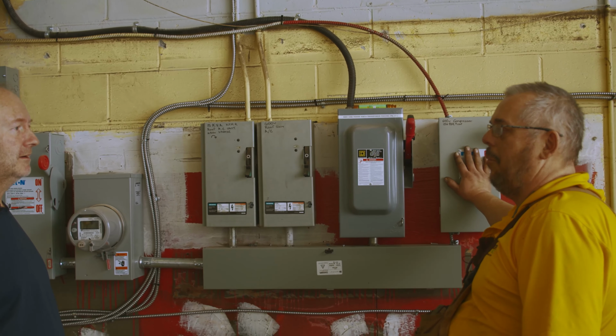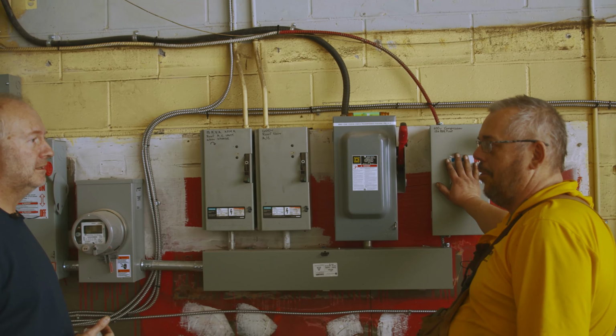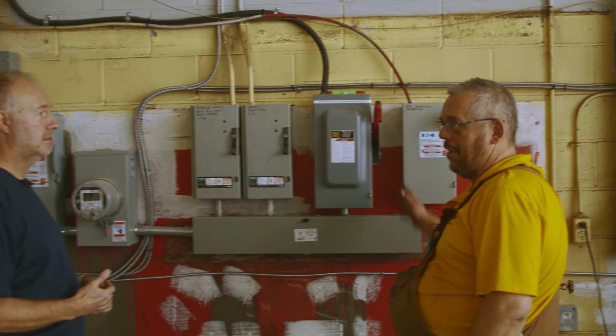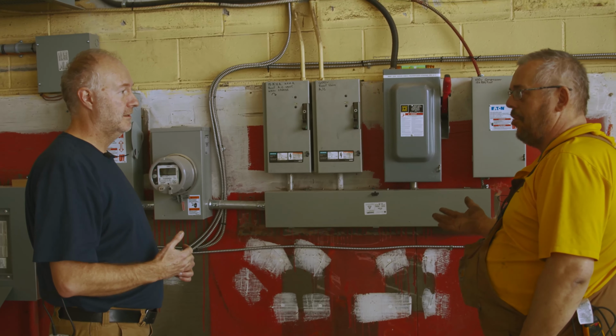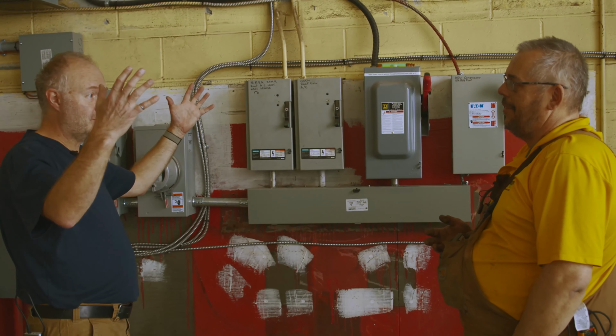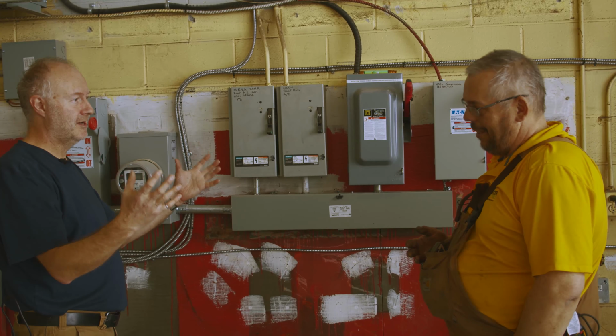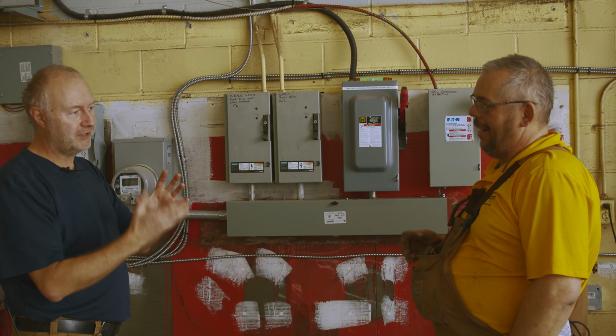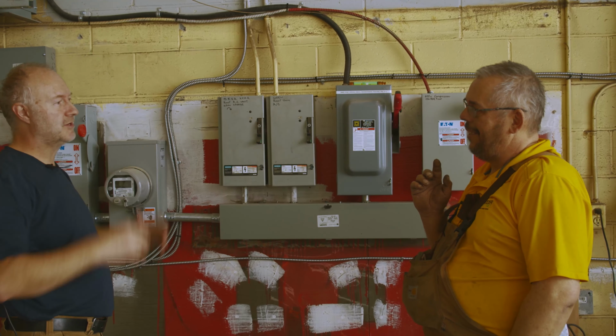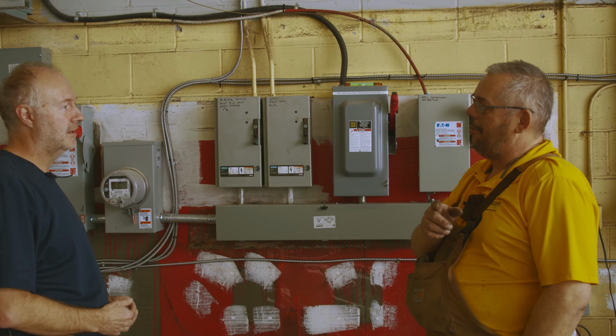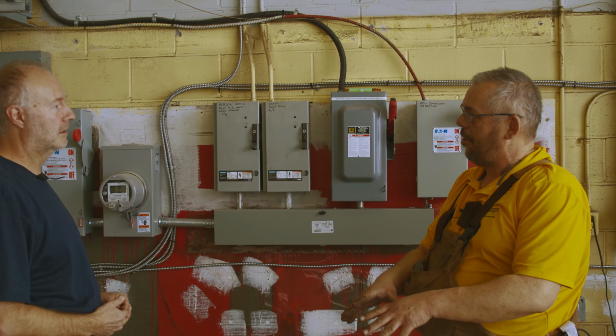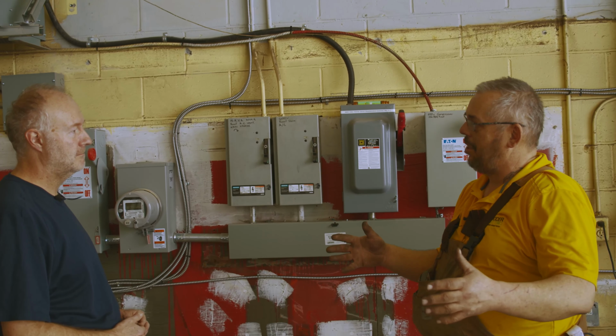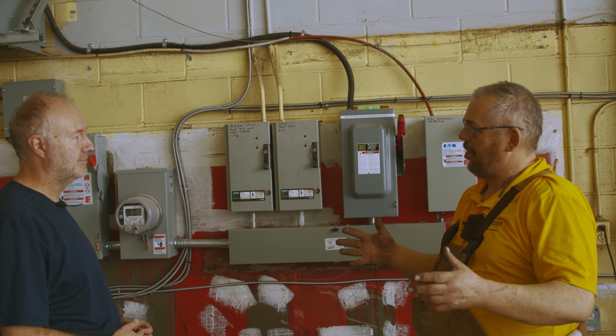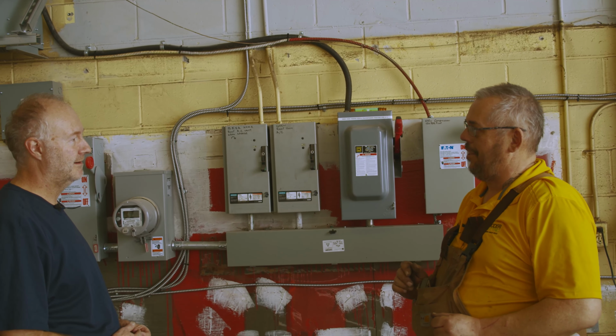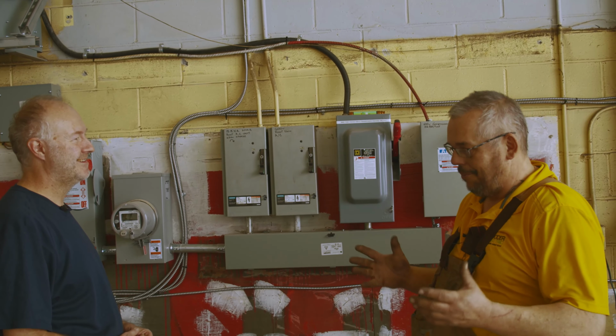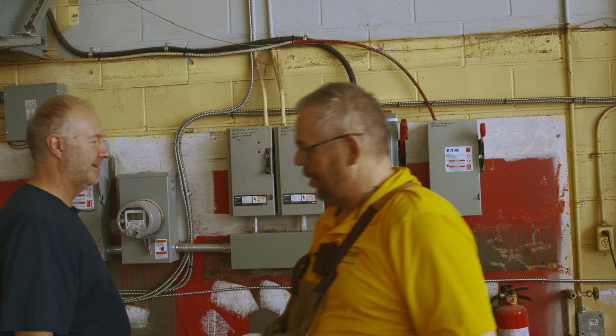The minimum wiring that we have in fuses is 15 amps, so it's protected at 15 amps, but it's very minimal draw compared to what you'd get. When you consider it's an enormous compressor with a 5 horsepower motor, but it's only drawing 5 amps because the voltage is so much higher. Exactly. But the compressor that was there originally from the shop that was here before you was actually about the same size, but it was a 60 amp compressor running on 208 instead of 600. Okay. So the motor was drawing a lot more amperage.